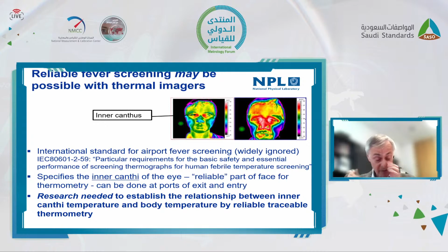There is a way of possibly doing it. There's an international standard which I helped write nearly 15 years ago for airport screening, and it mandates use of the inner canthus, this part of the eye, as the opportunity to measure body temperature. That was a compromise—there was some published evidence showing inner canthus temperature had some relation to body temperature measurement, but there's still work needed to establish that formal relationship between inner canthus temperature and core body temperature using reliable, traceable thermometry.